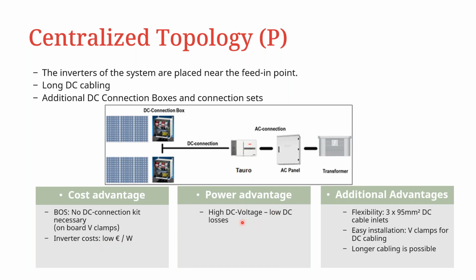The power advantage here is that you have high DC voltage, and therefore this can also reduce the power losses on the DC side. In terms of the additional advantages, you have the possibility to connect 3 strings now instead of the 24 or 22 that we talked about for the 100 kilowatt. But this is provided using 95 millimeter square cables. So there is easy installation because of the V clamps on the DC side, and longer cabling gives you flexibility on where to place these inverters.